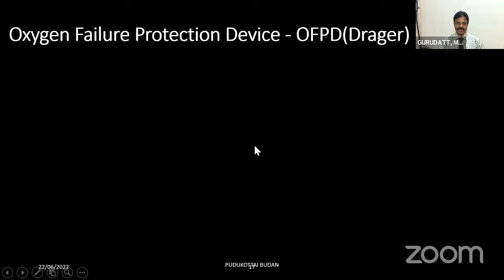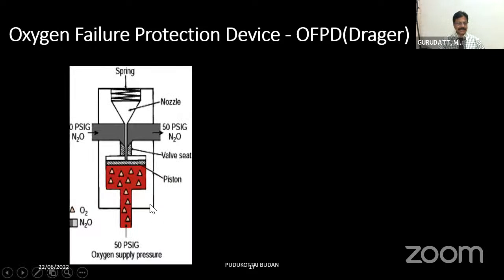So how do they work? Now slightly different when compared to the shut-off valves. Now here you can see this diagram. The oxygen is entering with a pressure of 50 psig. This is pushing a piston and preventing a nozzle away from the nitrous oxide tubing or nitrous oxide flow. So as long as the oxygen pressure is above 50 psig, this nozzle keeps away, and there is a complete continuous flow of nitrous oxide equal to 50 psig.